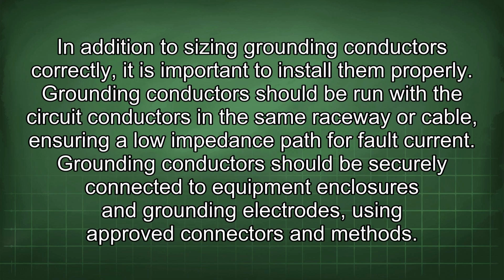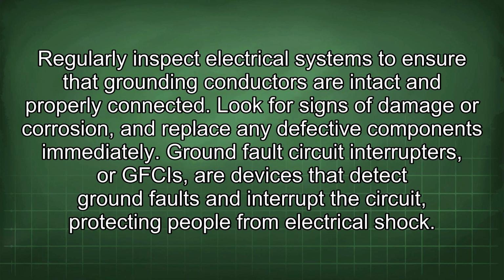In addition to sizing grounding conductors correctly, it is important to install them properly. Grounding conductors should be run with the circuit conductors in the same raceway or cable, ensuring a low impedance path for fault current. Grounding conductors should be securely connected to equipment enclosures and grounding electrodes, using approved connectors and methods. Regularly inspect electrical systems to ensure that grounding conductors are intact and properly connected. Look for signs of damage or corrosion and replace any defective components immediately.